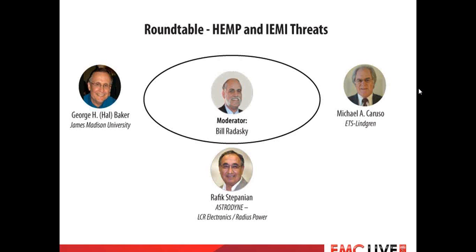The major point here is that lightning protection does not suffice for EMP protection. It certainly can help, but we need to be careful. There's a misconception out there that lightning protection will, in some large measure, protect against EMP. That's not true. The big benefit from lightning protection is if you have good lightning grounding, multi-point grounding for the buildings. That is a huge benefit for EMP as well, for diverting the EMP transients away from sensitive equipment to the ground.